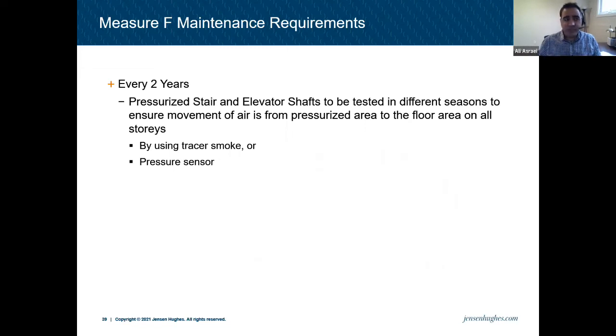If you want to skip a season, you have to provide a calculation. So if you can provide a good stack effect calculation, say, okay, I did this in the summer, this is the test result, but I am 100% sure it works in the winter too, because the stack effect that I'm getting in the winter is this and this and this. And now I can confirm that this system is going to work in the winter properly as well. If you want to do that calculation, or just do it in the next season. So every 2 years, the next time, do it in the winter and just make sure the system works.